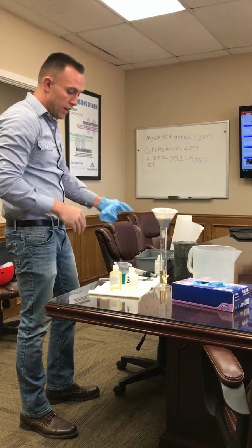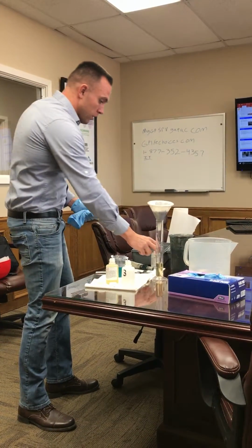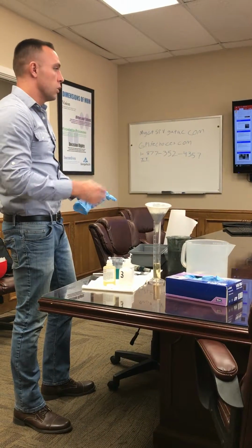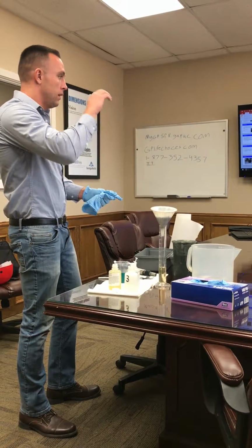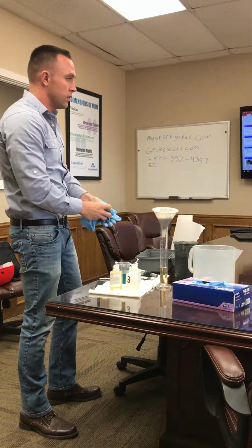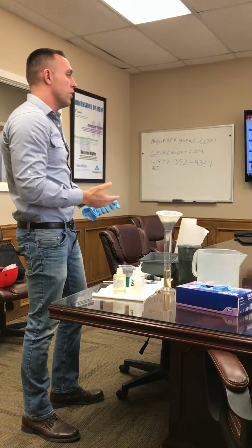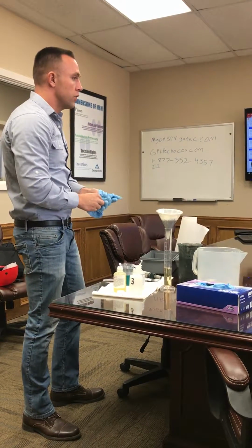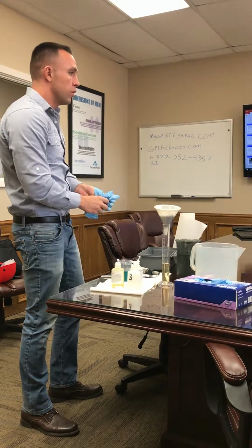So what I did was I added 0.4 of my initial chemical, which equals 20 gallons. So you go to the PLC screen, type in 20 gallons, or if you're adding it by minutes, that pump will pump 5 gallons per minute, so you'll do 4 minutes. I wrote the conversion sheet up for you guys. I'll hand one out to you before I leave.